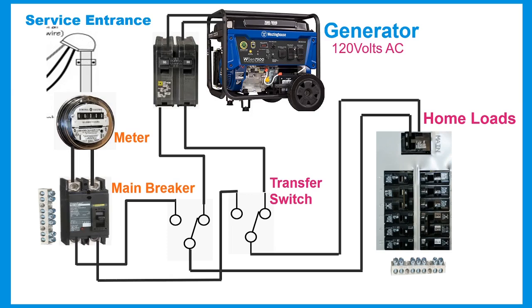An automatic transfer switch is mostly installed where a backup generator is located so that the generator may provide temporary power if there are power interruptions from the utility company. For example, if a backup generator is used to supply backup power when a public utility fails, the automatic transfer switch will tell the backup generator to start. Once the automatic transfer switch sees that the generator is ready to provide electric power, the ATS breaks the home connections to the electric utility and connects the generator to the home's main electrical power, supplying power to the home's electric load.